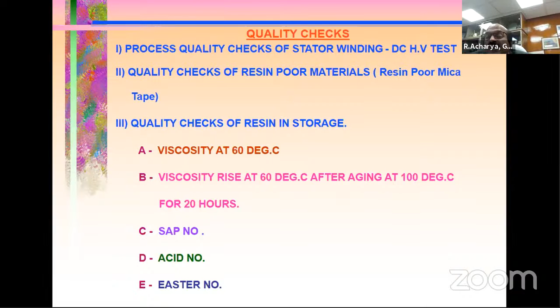It's the same resin. For a typical 135 to 140 ton job, when it is impregnated, it takes almost 60 kiloliters of resin and hardener mixture. And this is a reusable resin that has been practiced for large capacity machines. And the advantage of the VPI insulation system, which is actually the most important in the present relevance: a very high mechanical bond, a void-free insulation, a high dielectric strength, a very low dissipation factor, or you can say tan delta, hence longer electrical life, and better heat transfer.